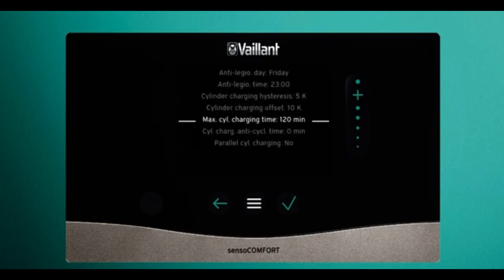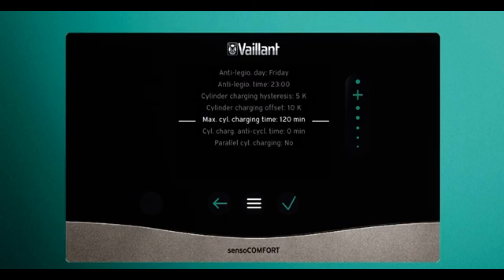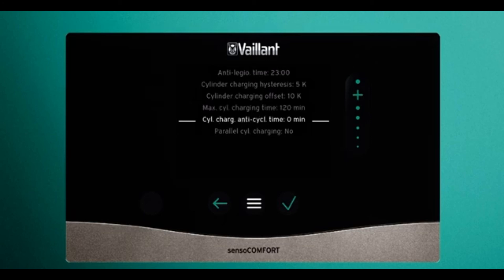Maximum cylinder charging time is the maximum time that hot water can be produced without interruption from any other influence. Cylinder anti-charging time is the wait time between hot water cycles. For instance, if you're running on timers with hot water only in the evenings and your tank is very cold, setting this too low may cause a long wait between heat-up cycles. I find it's best to set the maximum charging time to 120 — its maximum — and the anti-cycling time down to zero.